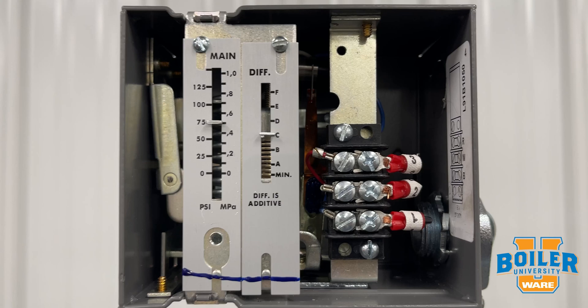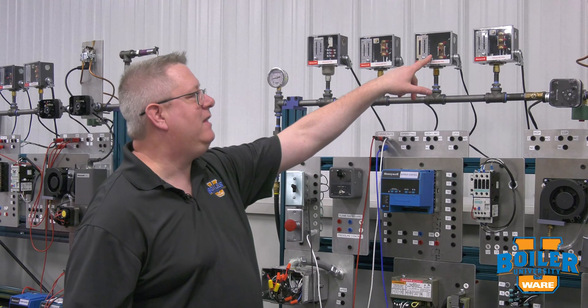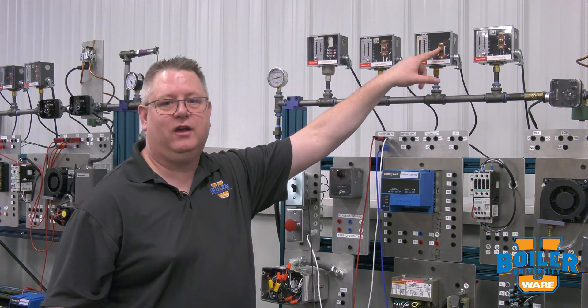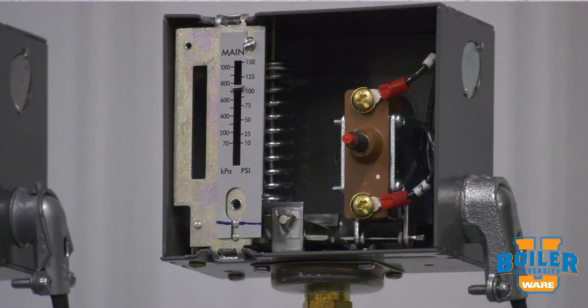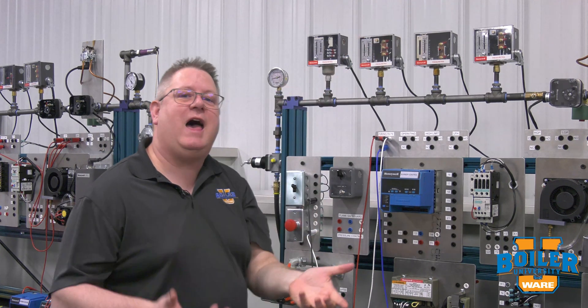If we take the cover off and look at that, we can see it doesn't have a switch mechanism like the other devices. Our high limit is easy to recognize because it has a manual reset button. On the new mercury-free styles, that's on the front, and on the older mercury styles it was frequently on the top.